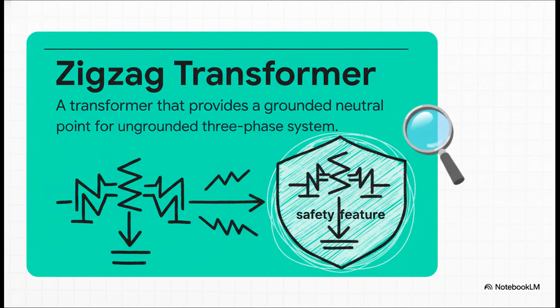And here it is, the hero of our story: the Zigzag Transformer. It's a super specialized piece of equipment designed to do one thing only, solve this exact grounding problem. At its core, its whole job is to create an artificial neutral point. Think of it like retrofitting a critical safety feature onto a system that was built without one. It literally establishes the safe path to ground that was missing all along.